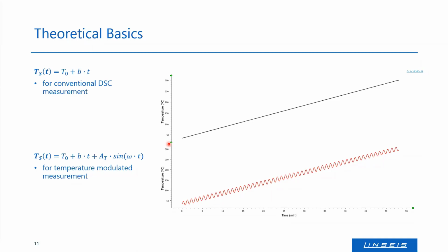And now we added the modulation, what you can see here below. So basically it's the same for the rise of the average temperature. You have the starting temperature, room temperature or below for cooling options, plus the average heating rate multiplied by time. But what we add now is an amplitude. So this is the amplitude of the temperature modulation you can see here, multiplied by the sine of omega and time. So this is how we receive the result here. This is basically just what we do for the temperature.